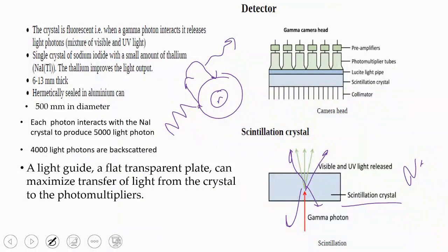This light photon I receive on a specific light guide, and then I connect it to the photomultiplier tube. I connect it to the photocathode of the photomultiplier tube so that it converts to an electron. After that, I perform multiplication on this electron inside the photomultiplier tube and convert your signal.